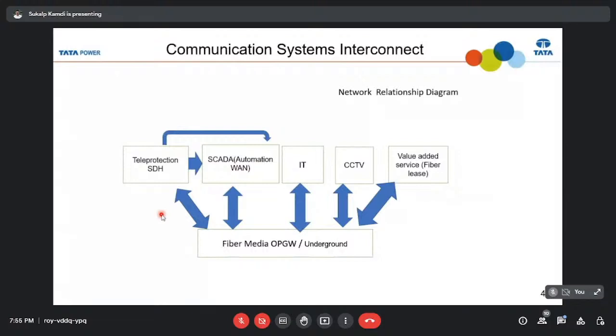This matter of 1 second or milliseconds matters because the protection system has to be accurate enough. Whatever electrical faults happen, the latency involved is in milliseconds and microseconds. So this fast means of communication and protection is possible only through fiber optic, wherein light, or higher wavelengths of light, is the media used to transmit signals. The overall latency in the network at Tata Power is maintained up to 7 milliseconds maximum. Otherwise, if there is a delay in the signal reaching the other station and there is a fault, the entire purpose of the communication system fails. So teleprotection, or protection of high voltage equipment, is the major application of the communication system here.